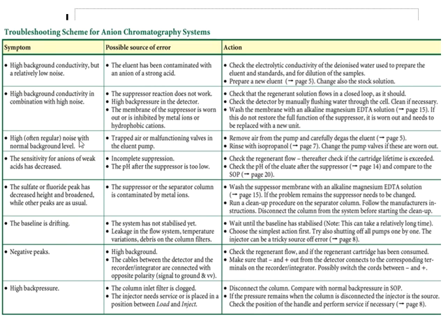Next, high noise with normal background level. That probably means that you've got air in your system. So purge your pump and rinse everything out with alcohol. That typically will fix the problem a little bit better.